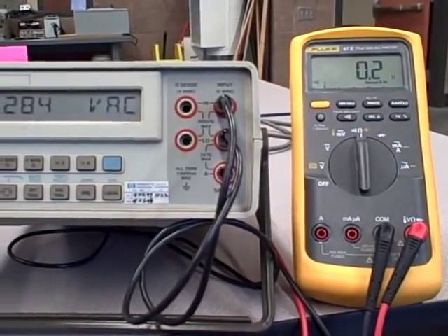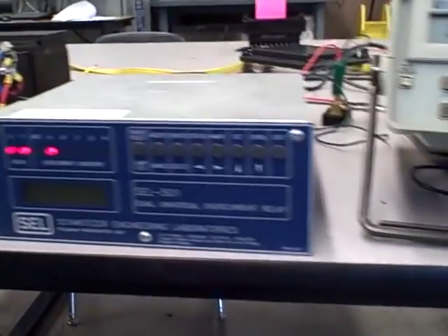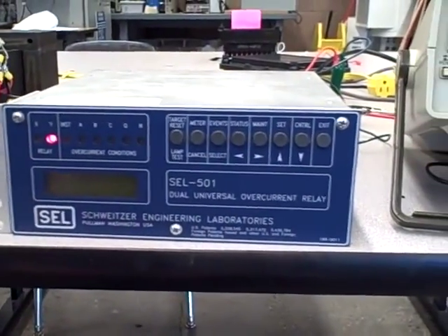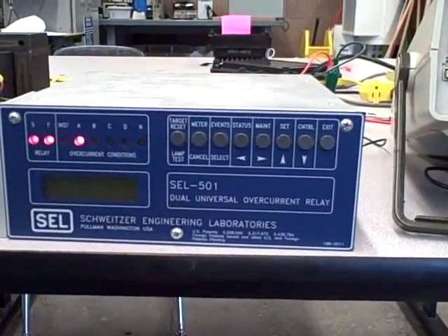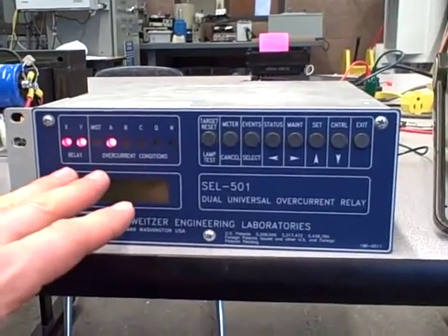So now I'm going to reduce the current. When I reduce the current, you hear the annoying beep go away, because as the breaker has been tripped and opened, the current falls to 0 and it's no longer trying to trip the breaker, so the contact opens. But notice it still maintains a record of the trip event.